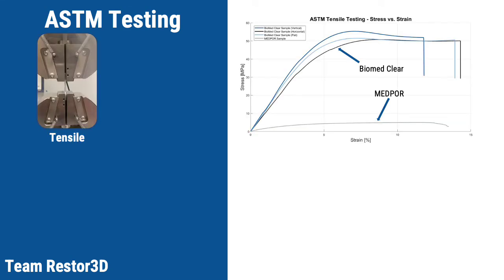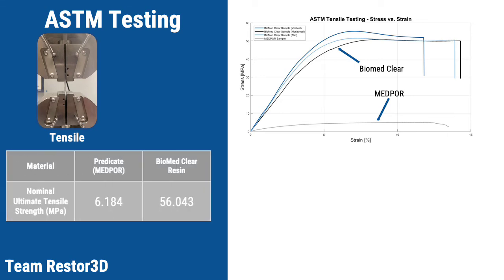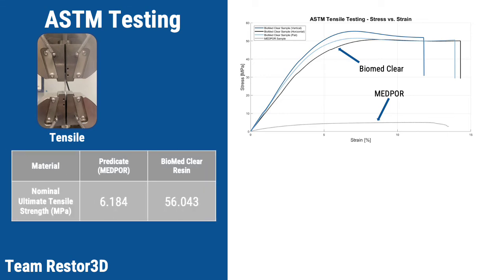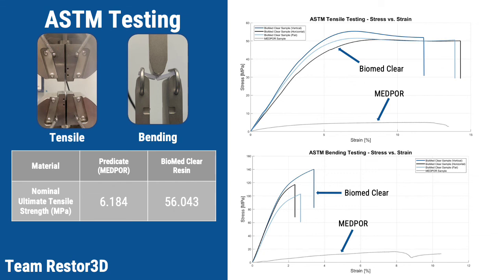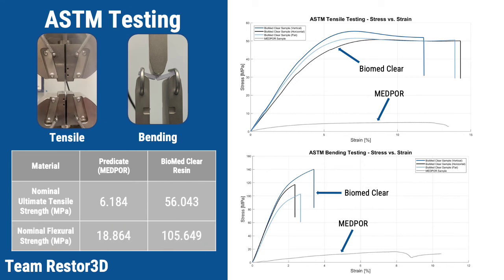In our case, the predicate performed tensile and bending testing, so these were the ASTM standards used for testing. The tensile testing results show that the nominal ultimate tensile strength value of Biomed Clear is about 50 megapascals larger than that of the MEDPOR predicate. The bending testing results show that the nominal flexural strength value of Biomed Clear is almost 100 megapascals larger than that of the MEDPOR predicate.